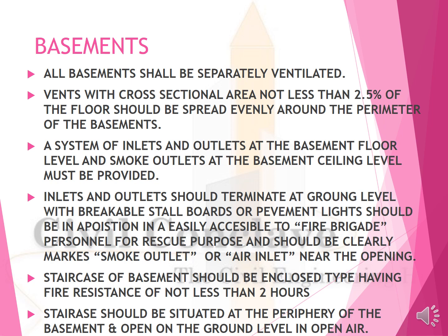Basement. All basements shall be separately ventilated. Vents with a cross-sectional area not less than 2.5% of the floor area should be spread evenly around the perimeter of the basement. A system of inlets and outlets at the basement floor level and smoke outlets at the basement ceiling level must be provided. Inlets and outlets should terminate at ground level with breakable stall boards or pavement lights, should be in a position easily accessible to the fire brigade, and should be clearly marked smoke outlet or inlet near the opening.